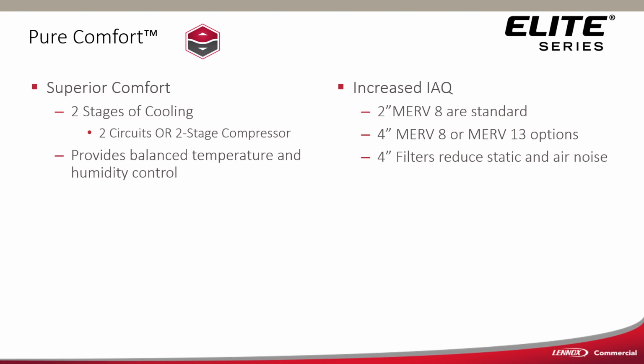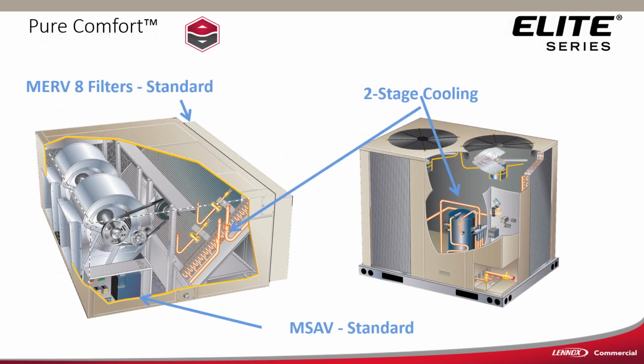This comes with an external filter rack that will accept a 4-inch filter. So we can go up to MERV 13, and you can buy other filters out there that are 4-inch that'll go higher than that. Because this has got MSAV and it's 2-stage, we have a variable frequency drive in there. So we're going to have a soft start, which is going to keep the sound levels down, and it's part load, which also helps keep the sound levels down. Looking at that, you're seeing our 4-inch filter rack. You can put 2-inch filters in there, but you can also put 4-inch filters in there. And on the bottom, you're seeing our variable frequency drive for our MSAV that's standard on that. And over to the right on the condensing unit, you see the single circuited 2-stage compressor.